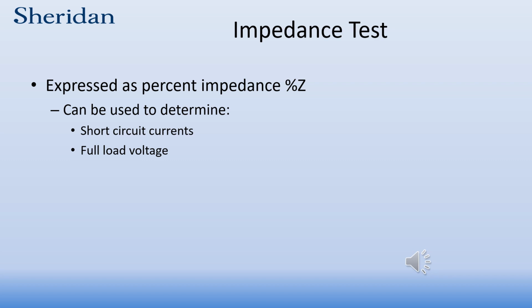Impedance of a transformer is expressed in percent impedance, and you'll see it on the nameplate of the transformer, percent Z. It can actually be used to determine short circuit currents and full load voltage.